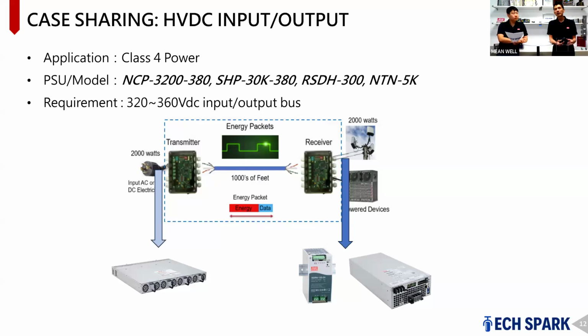Yes. A lot of AC to DC power supplies you see on the spec go up to 370, 380 VDC or 400 VDC. They can all be used with it. The only issue is it needs further evaluation when doing the safety certification for the system.